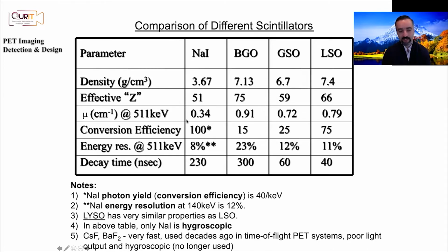and conversion efficiency. So sodium iodide is very good in conversion efficiency. Once it absorbs, it really produces significant scintillation. So you can sort of see that even though BGO was not the best, LSO comes close. So LSO is very nice. It's very effective at stopping incoming gamma radiation and also in converting it into scintillation.